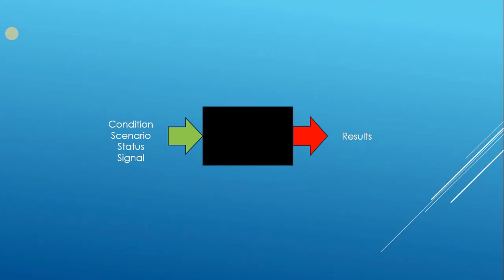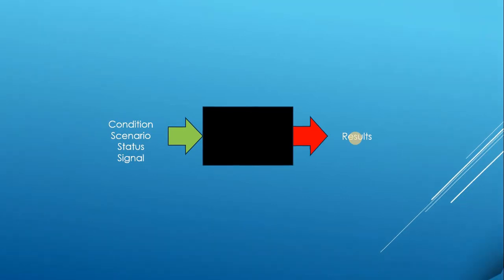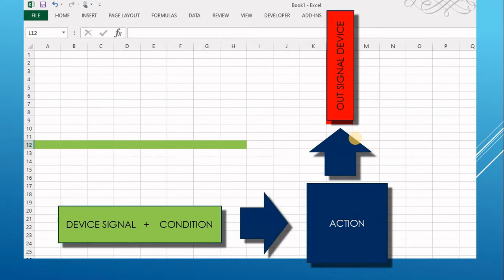Hello and welcome to a new video. This video will talk about one of the design documents generated by the instrumentation and control guys, called the cause and effect. In the DCS or PLCs you need to program based on a document from the designing company or EPC company. The cause and effect does not tell the programmer how to program his PLC or DCS; rather, we give them conditions, scenarios, status, or signal values, and tell them when this happens, give us these results — close this valve, open this valve, stop the pump or motor.